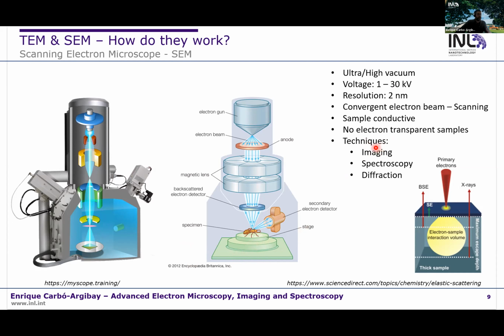What are the main features of this technique of scanning electron microscope? Basically, the resolution we can reach with this technique in terms of imaging resolution is 2 nanometers, even 1 nanometer. The sample must be conductive, but this is not a problem. We have sample preparation equipment to make the samples conductive, depositing a layer of metal or a layer of carbon on the sample. We can make it easily conductive, and the samples don't need any additional preparation. So we don't need thin samples or other specifications. So we basically can take a bulk sample, place it in the sample chamber, and scan the sample with the electron beam. The resolution, as I told you, is around 2 nanometers.